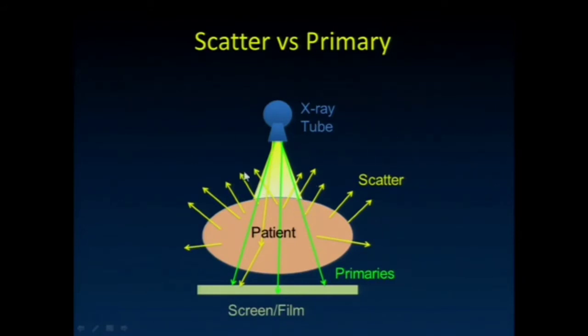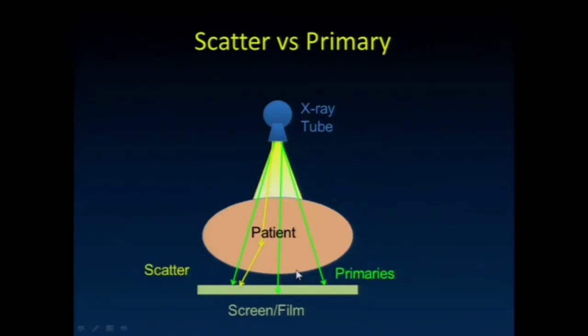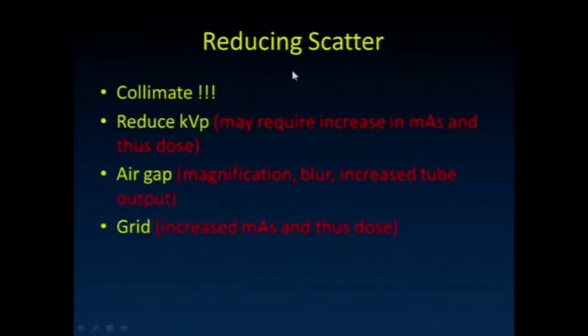Here's the patient—all those scattered x-rays coming out. I emphasize again that many fewer make it through the patient. Here I've shown a scatter-to-primary ratio hitting the screen closer to one-to-three, but the true number is actually closer to three-to-one—more scatters than primaries. We're ignoring everything that was absorbed completely or back-scattered and didn't hit the detector.